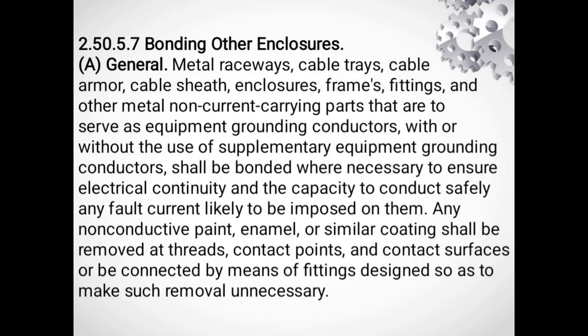And 2.50.5.7 Bonding other enclosure. This extends the bonding requirements to other enclosure. Metal raceway, cable trays, and other enclosures must be bonded to ensure electrical continuity. This creates a continuous ground fault current path throughout the electrical system.